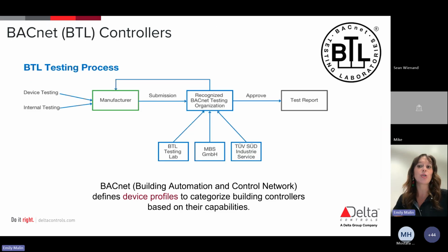But when we talk about controllers, what are we really talking about? For our purposes, we're going to focus specifically on BACnet controllers. We've talked about this before. BACnet is just the building automation control network. But how are these really being defined? There is BACnet Testing Laboratories, an organization that ensures the proper implementation of all of our BACnet products. They provide an industry standard test suite, and they issue certificates to manufacturers that pass all of these independent tests.